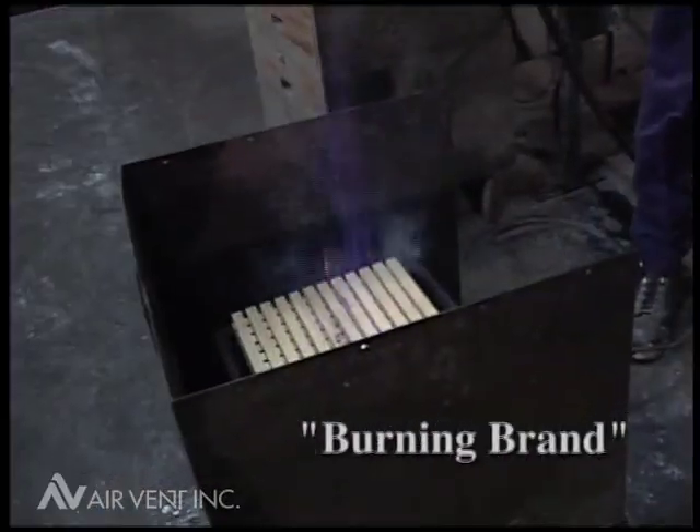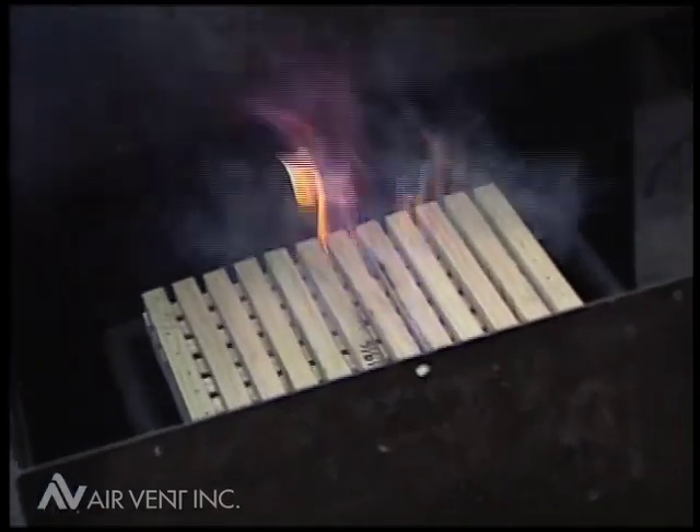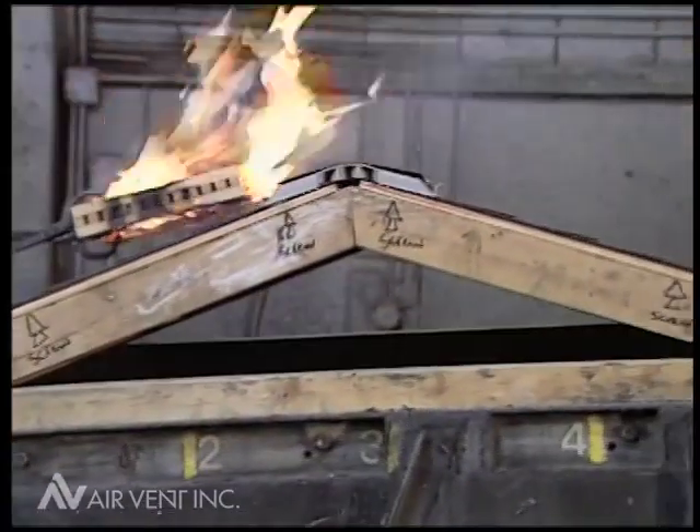In the burning brand test, 36 strips of Douglas fir lumber are nailed together and ignited in still air with an igniting temperature in excess of 1,600 degrees Fahrenheit.